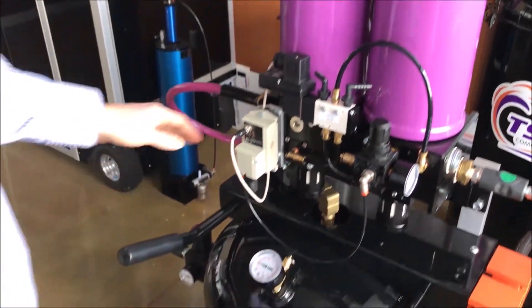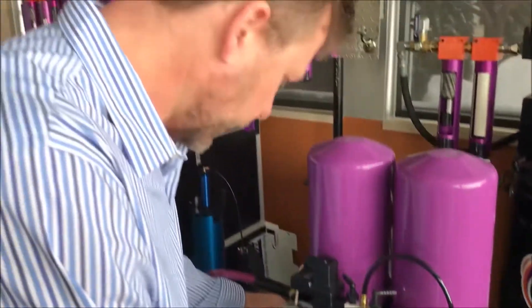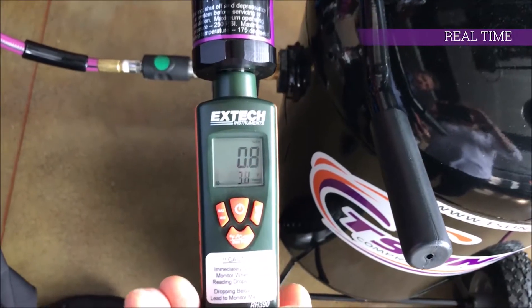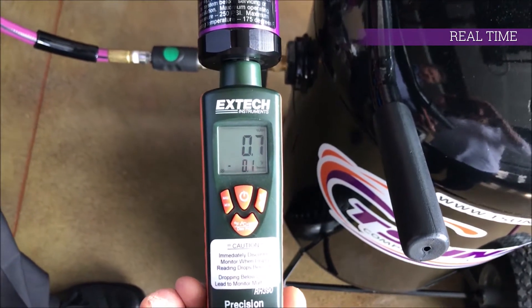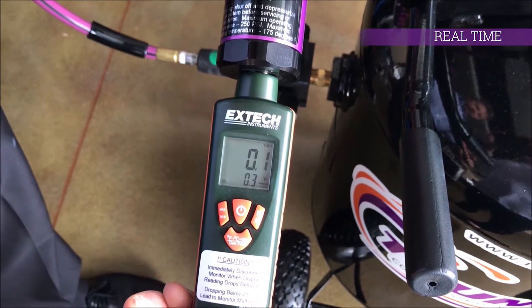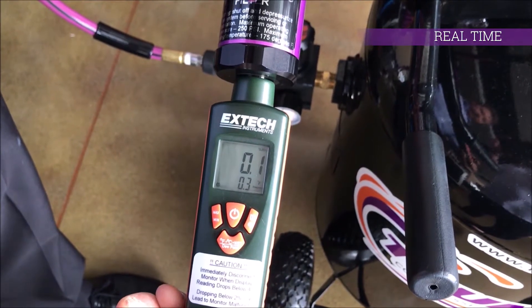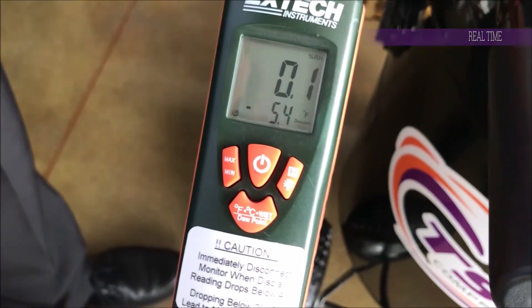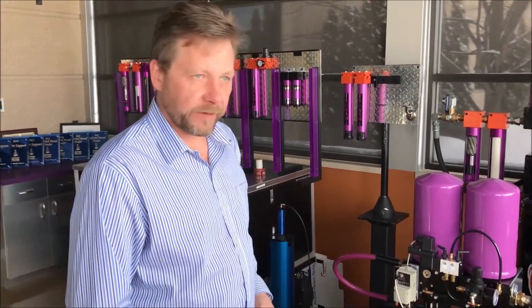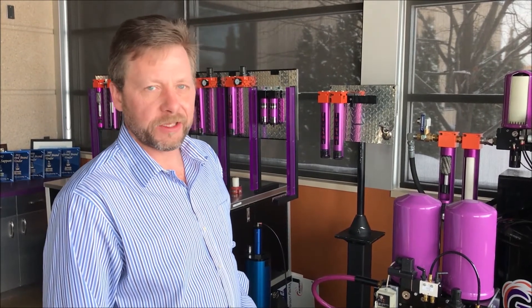Here's an example of what you can expect as far as air quality. This regenerative dryer was able to take our relative humidity down near zero percent, and the dew point was at minus five degrees and dropping.